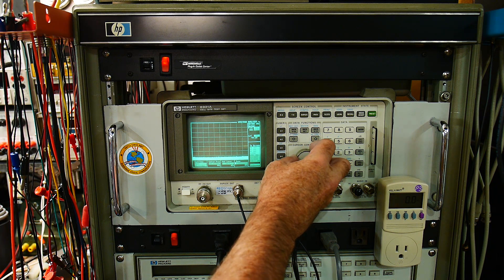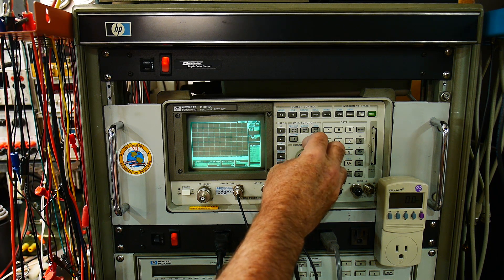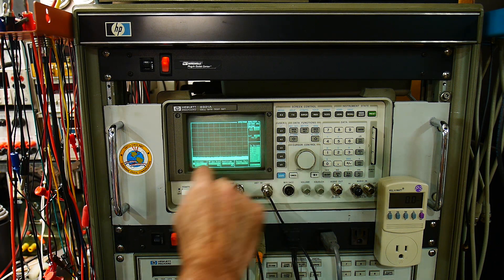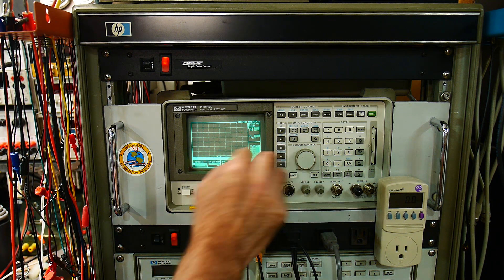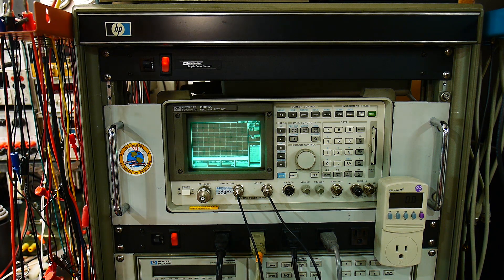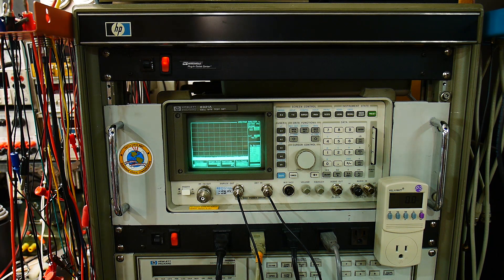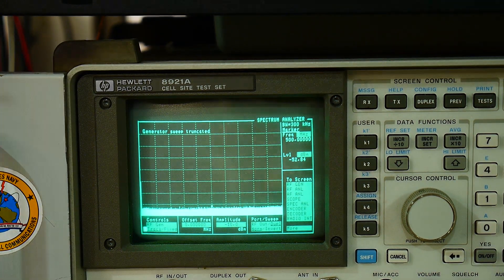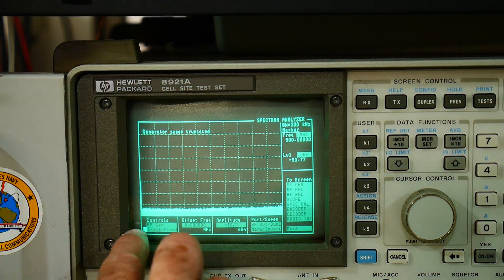The next thing we need to do is go here to control, say main, and we'll go to the RF generator. It says tracking or fixed. It's set to fixed right now, so we'll say track. You guys can't really see that, can you? OK, I'll go to track.